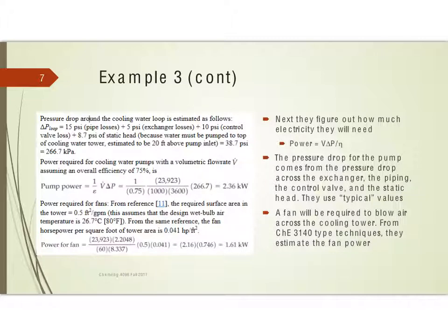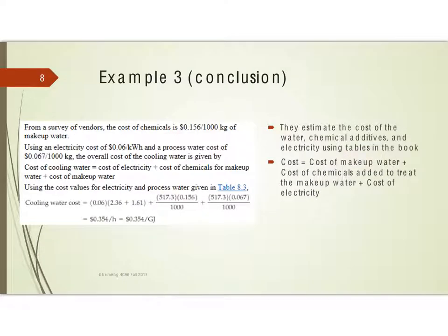And then, they also need to have the fan to blow the water across the cooling tower. And they just do some simple estimates for that. Then, they just estimate the costs. So, we've got water, we have some chemical additives, we've got electricity. They use the tables in the book. And they add all those up, and they come up with a cost of 35.4 cents per gigajoule, is their 2001 estimate of the cost of cooling water.